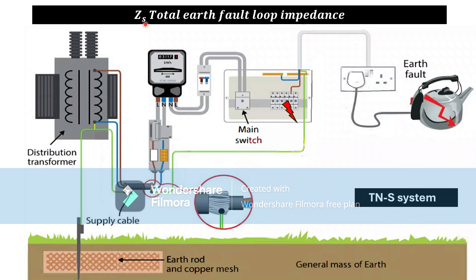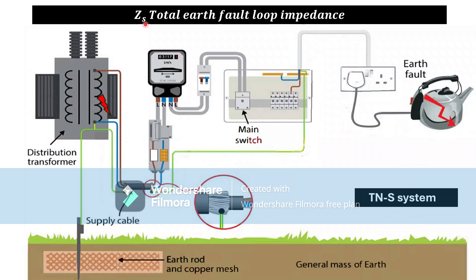For each type and rating of socket, there are different Zs values in the 18th Edition book. Our measured Zs values, measured in ohms, need to comply — they must be as low as possible. For example, for a B32 breaker, the book states 1.37 ohms, so when we measure Zs it should be below 1.37 ohms, meaning it is complying and our breaker will trip on time.